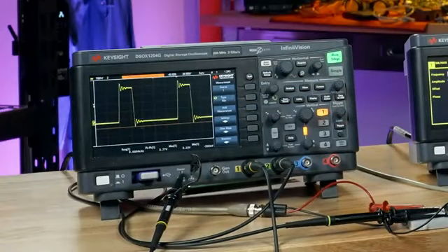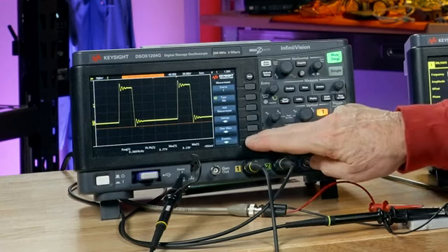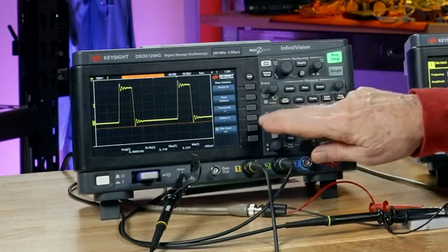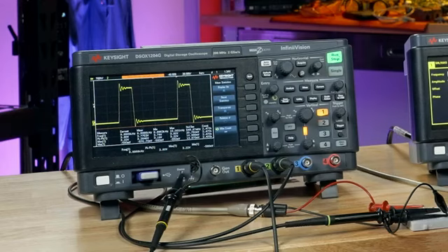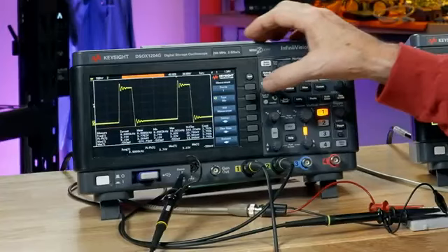Right now I've got 4 measurements on screen. That's the maximum on this scope. All of our higher performance scopes can show many more measurements than this, up to 10 measurements simultaneously. Now we can also turn on statistics for these 4 measurements, and I can see the average, the minimum, the maximum, the standard deviation, as well as the number of measurements that have been accumulated in this statistical set so far. Now if I select additional measurements, the one that I selected the earliest just slides off screen and you get the last 4 measurements. So let's select some additional measurements.